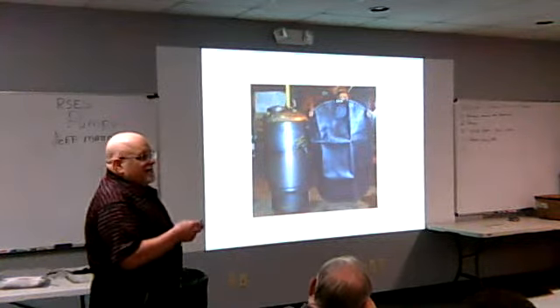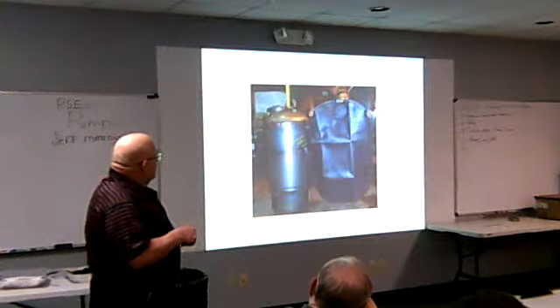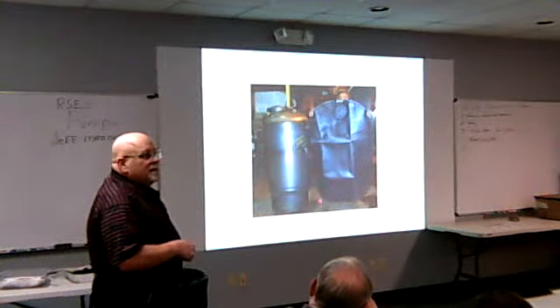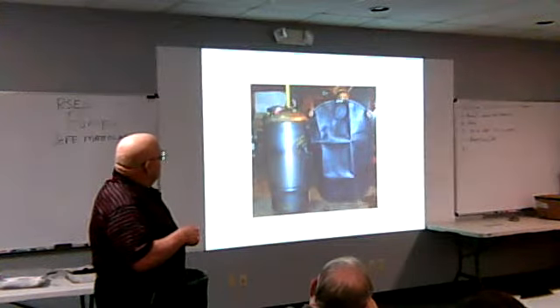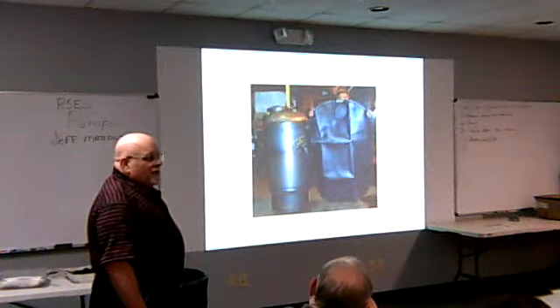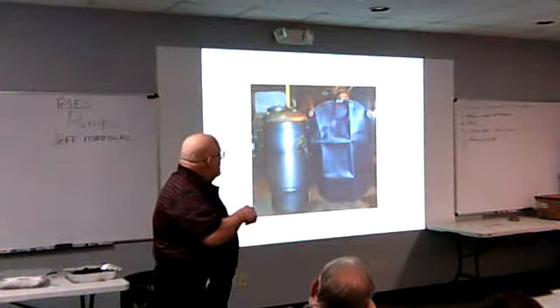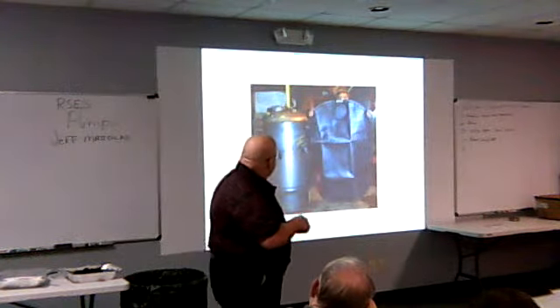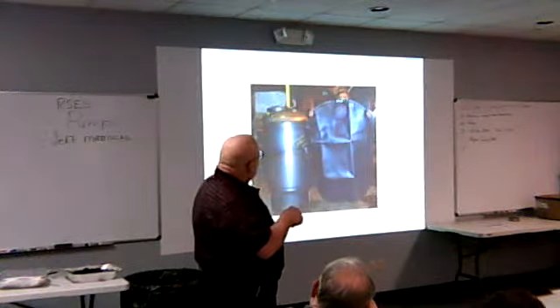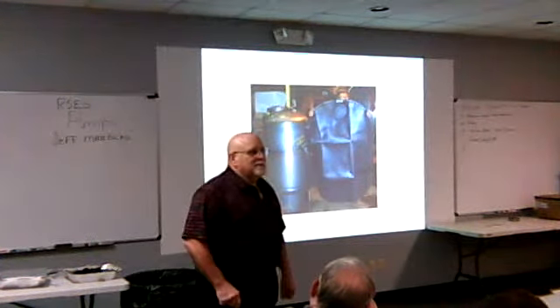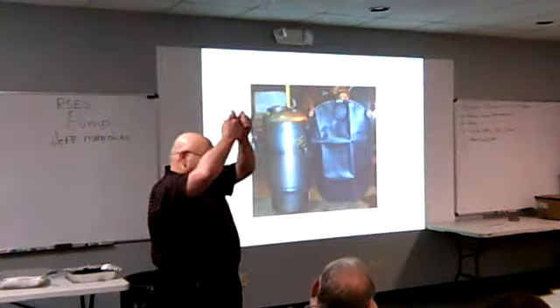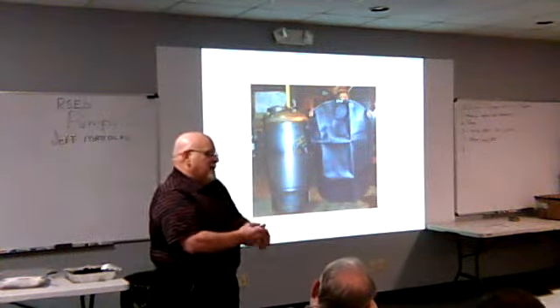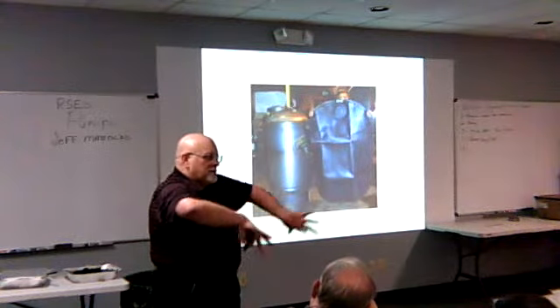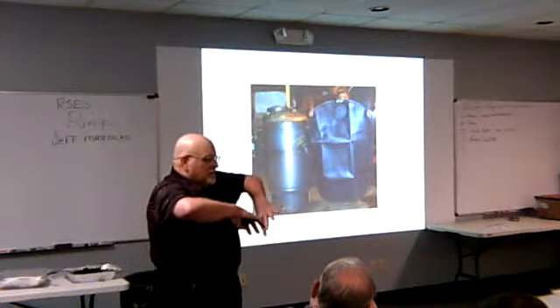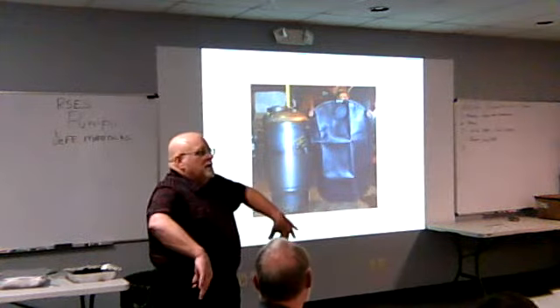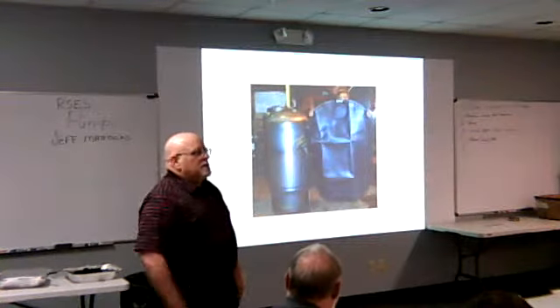This is your CA tank. This is the one you can use that rule of thumb on. This bladder mirrors this entire tank. This is your gasket on top. How do you get that thing out of it? Chain fall and a choker. Lay the tank down, chain this, hook the choker around this and crank it out. You put them in, they use a 2x4 to slide them in. And then once you get them in, you put air in to expand the bladder. Not fully, just enough air to blow it out. And then put your lid back on and then charge it.